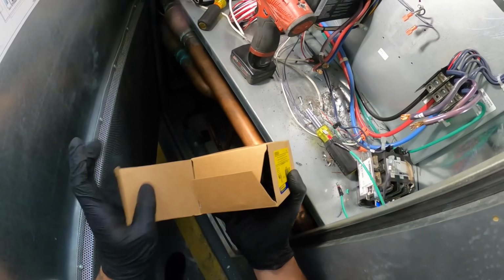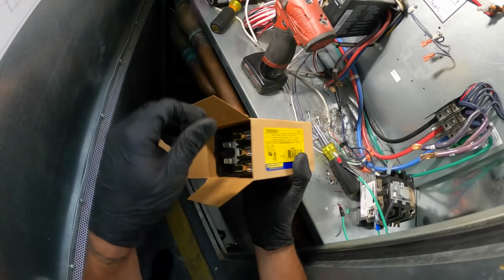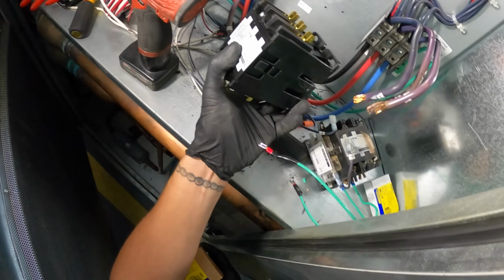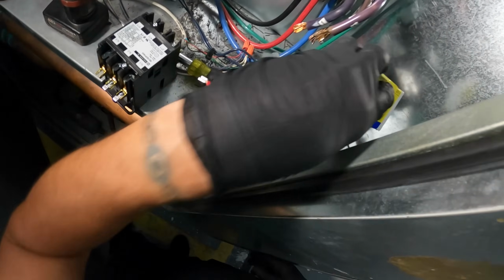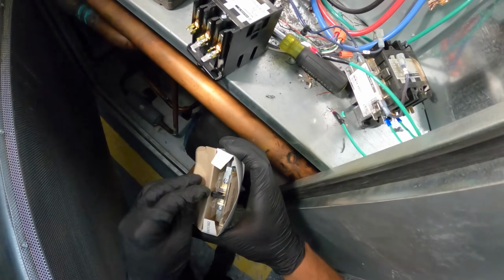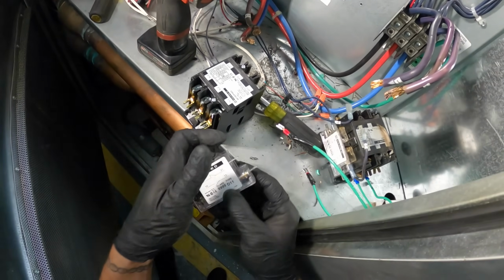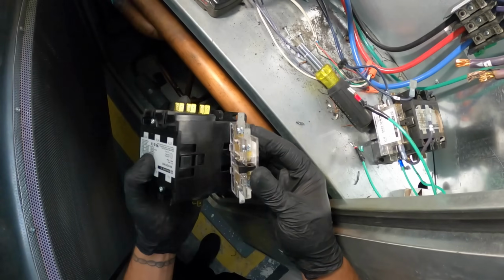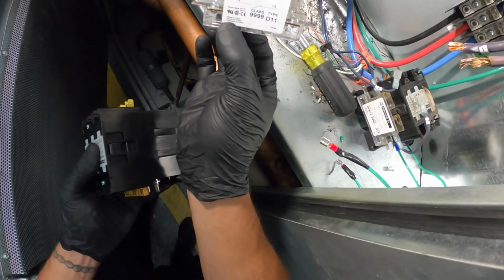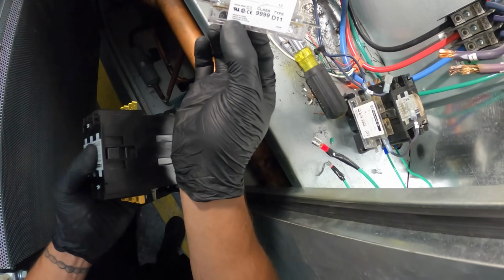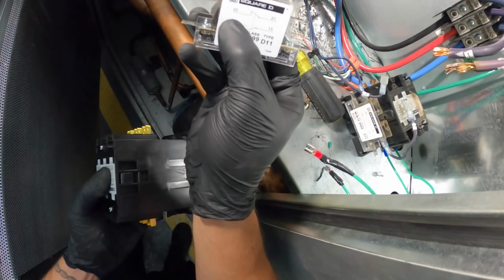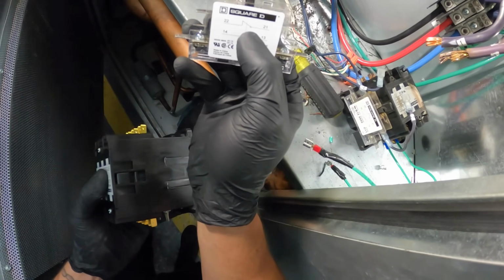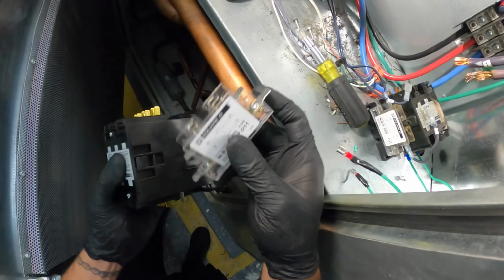Now we can take our new contactor here. This is a big contactor, but I got the same exact one, which is nice. And it has this auxiliary contact on there. Let's see how to put that on. It's the exact piece. So here we have a type D11 Square D auxiliary contact. Between 22 and 21 is normally closed, and 14 and 13 is normally open.